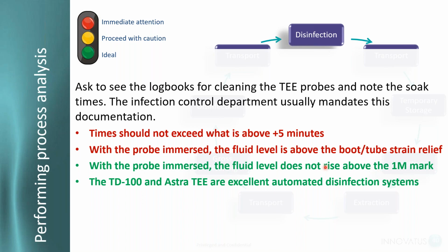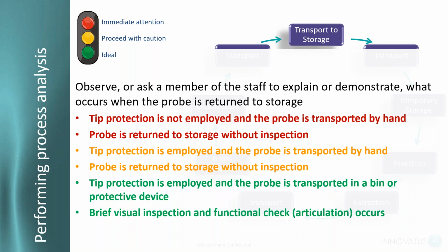And I'm a big fan of automated disinfection systems because a lot of them have built-in leakage testers. You insert the probe into the automated system, and it does the leakage testing. It will cycle the disinfectant through the probe for the recommended period of time, and then it will do a clean water rinse. By the time you pull out the probe, you're done. So I'm a huge fan of those. They dramatically reduce margins for error and touch times.